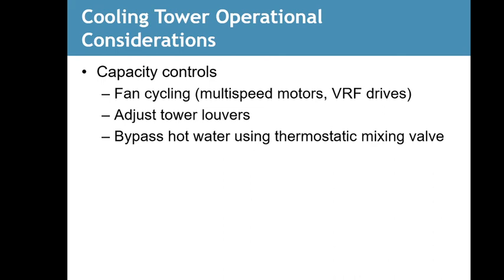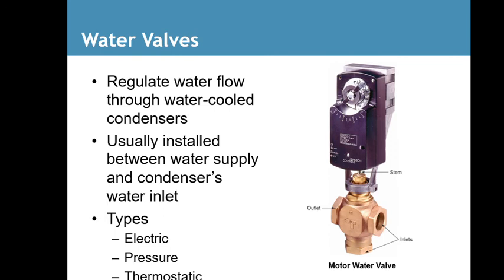Cooling tower operational considerations: capacity controls include fan cycling, multi-speed motors, VFD drives, adjusted tower louvers, and bypassing hot water using a thermostatic mixing valve. Water valves regulate water flow through the water-cooled condenser, usually installed between the water supply and the condenser water inlet. Types are electric, pressure, or thermostatic. For this, you would either have an electric sensor that would tell you when to add water. Pressure opens up under certain pressures, and thermostatic takes the temperature of the water, opening at that point.